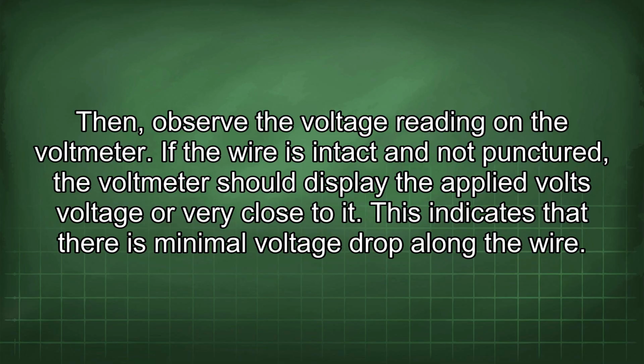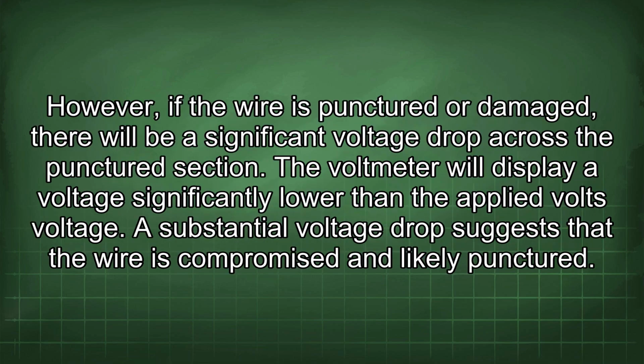If the wire is intact and not punctured, the voltmeter should display the applied voltage or very close to it. This indicates that there is minimal voltage drop along the wire. However, if the wire is punctured or damaged, there will be a significant voltage drop across the punctured section. The voltmeter will display a voltage significantly lower than the applied voltage. A substantial voltage drop suggests that the wire is compromised and likely punctured.